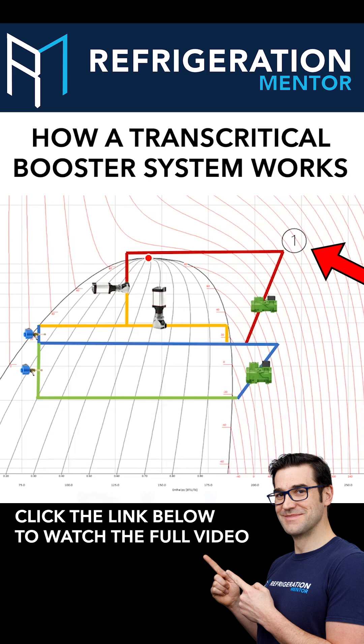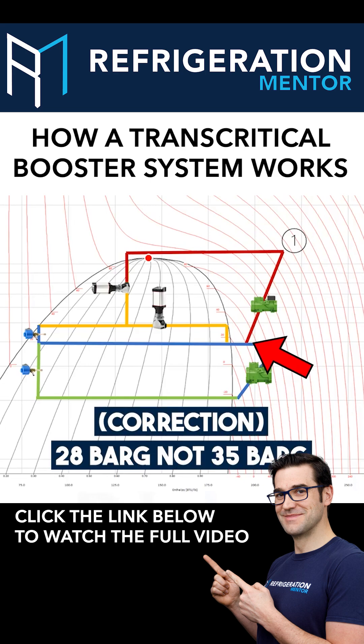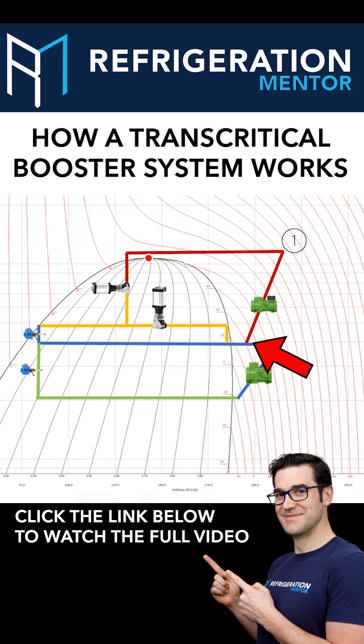So in this example here, we're at about 400 PSI, probably 35 bar-ish, and you're going into that transcritical mode. So you're in the middle of summer, it's 45 Celsius, 110 degrees Fahrenheit out, and all of a sudden, you're going right into critical, above the critical point.